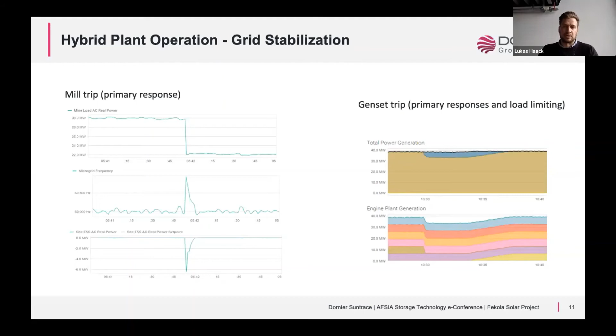In this case there's an engine trip, and the remaining engines are at a high load, running at about 90-95%. They should not cover this load because they would be overloaded for a short period. So the battery jumps in, provides primary response, and discharges power to fill the gap, giving operators sufficient time to start an engine and return to normal operation.